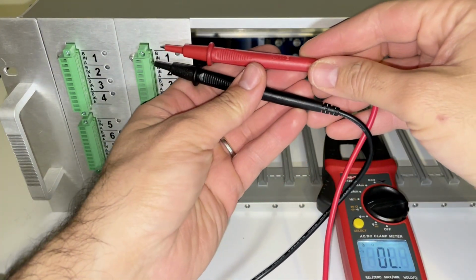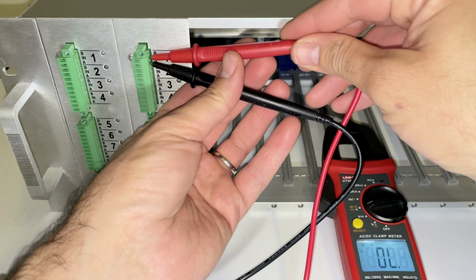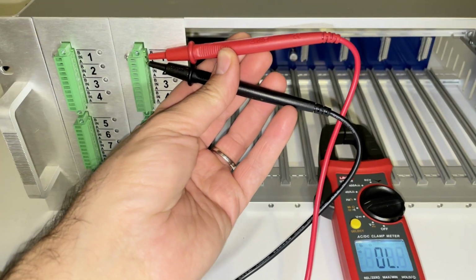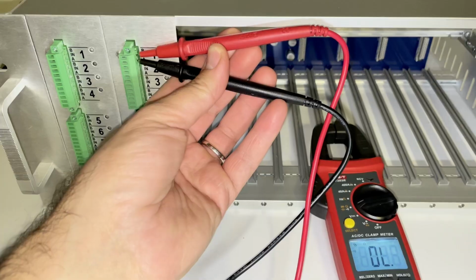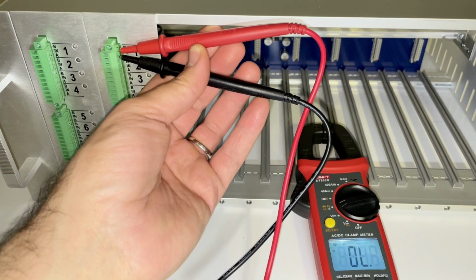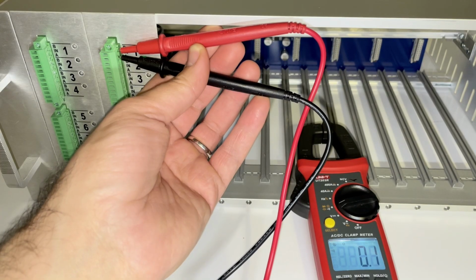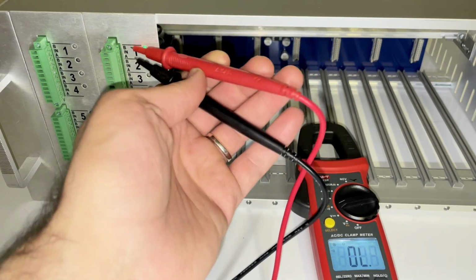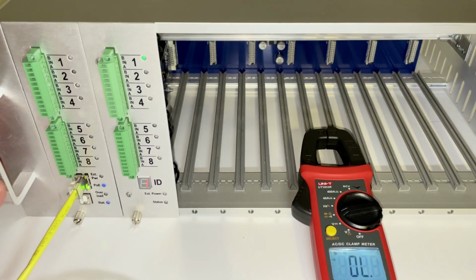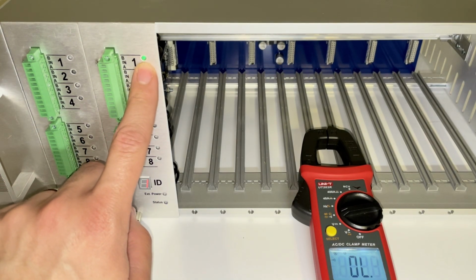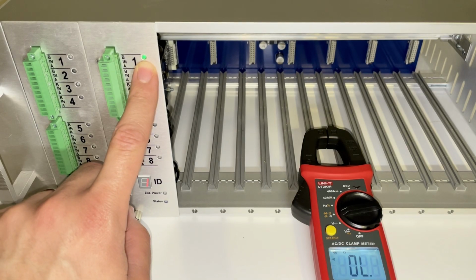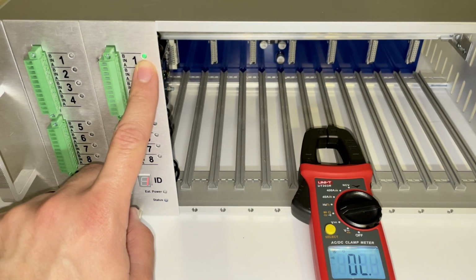Place the black probe on the common terminal and the red probe on the normally open terminal. Trigger the system. If the system is newly installed, ButterflyMX Support can assist with triggering. When the system is activated, the multimeter will produce a beep that lasts for the duration of the trigger signal. An LED indicator light is located above each relay, allowing you to visually identify which relay is activated.